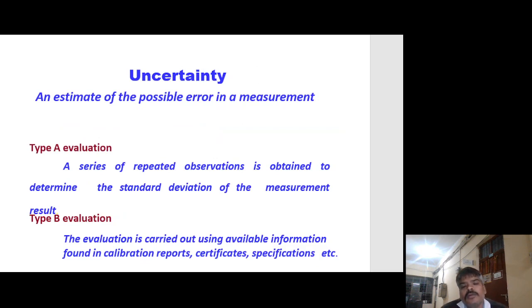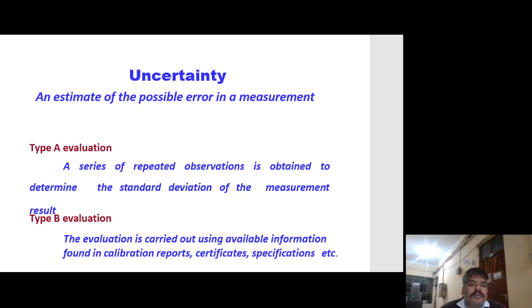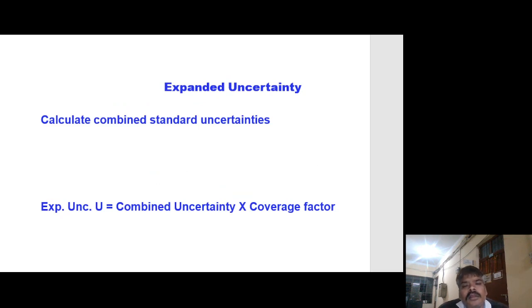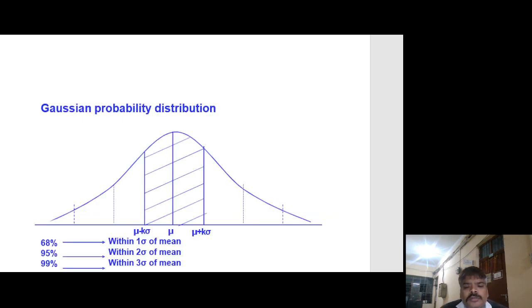Type A evaluation: a series of repeated observations is obtained to determine the standard deviation of the measurement result. Type B evaluation: the evaluation is carried out using available information found in calibration reports, certificates, specifications, etc. Expanded uncertainty is calculated as combined standard uncertainty multiplied by a coverage factor. For a Gaussian probability distribution: 68% of results lie within one sigma of the mean, 95% within two sigma, and 99% within three sigma.